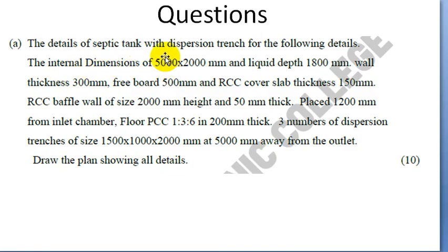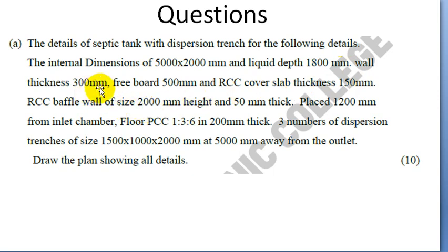Let's look at the details of the septic tank with dispersion trench. Internal dimensions: 5000 by 2000 mm. Liquid depth: 1800 mm. Wall thickness: 300 mm. Freeboard: 500 mm. RCC cover slab thickness: 150 mm. RCC baffle wall size: 2000 mm height by 50 mm.